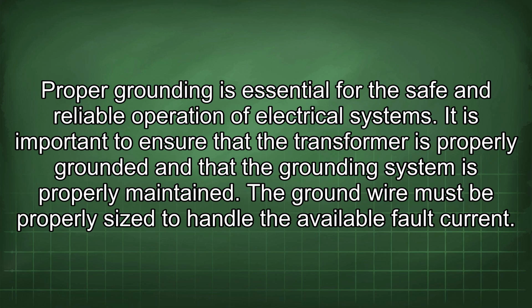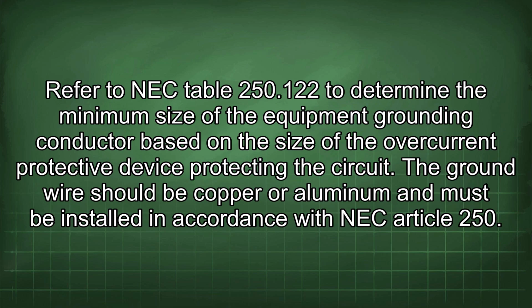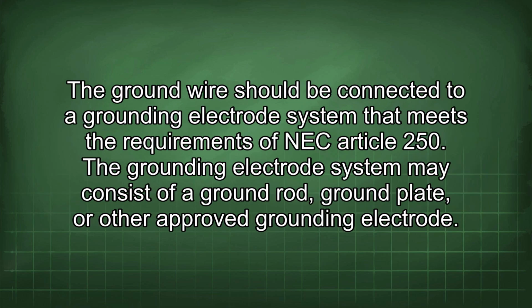The ground wire must be properly sized to handle the available fault current. Refer to NEC Table 250.122 to determine the minimum size of the equipment grounding conductor based on the size of the overcurrent protective device protecting the circuit. The ground wire should be copper or aluminum and must be installed in accordance with NEC Article 250. The ground wire should be connected to a grounding electrode system that meets the requirements of NEC Article 250.